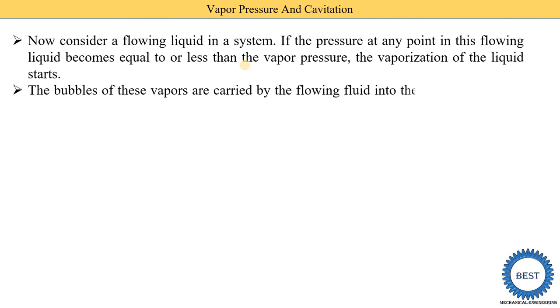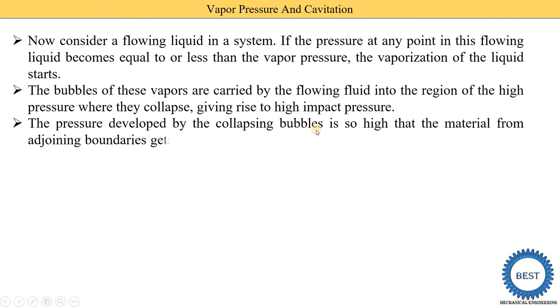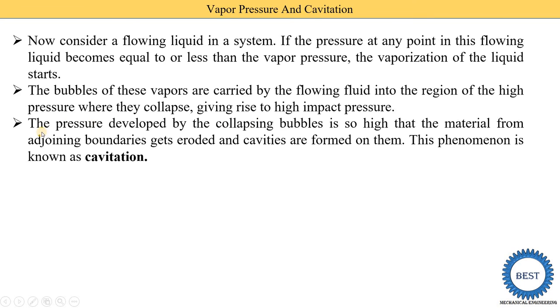These bubbles of vapor are carried away by the flowing liquid into a region of high pressure, where they collapse, giving rise to very high impact pressures. The vapor bubbles are created in the low-pressure region, flow with the liquid, and upon reaching the high-pressure region they collapse. When these vapor bubbles collapse, the pressure developed is so high that material from adjoining boundaries gets eroded.